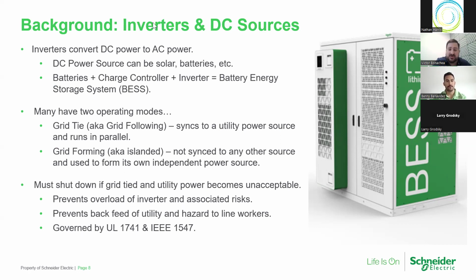It's a charge controller that takes energy and uses it to charge the batteries, be that power from solar, power from the utility, wherever it's coming from. It charges the batteries at the proper rate, at the proper current, so you don't burn the batteries or overcharge them. And lastly is the inverter, which is used to discharge the batteries and pull that DC voltage off of them, convert it to AC, and then feed it into your electrical system or AC loads.